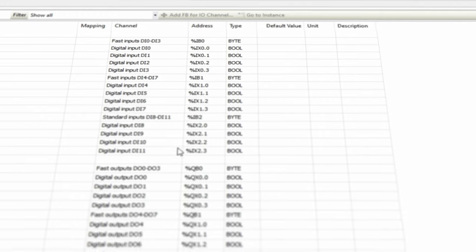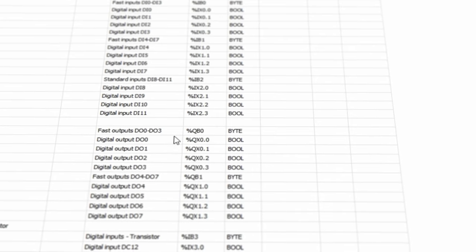Next step is to handle IO mapping. In general, all IO channels have unique address identifiers. But unless you really know what you're doing, it's a bad idea to use those addresses in your control application. Instead, symbolic variable names are usually used. And the process of attaching variable name to the specific IO channel is called IO mapping.